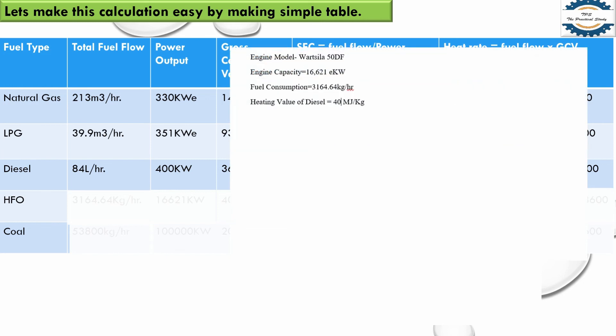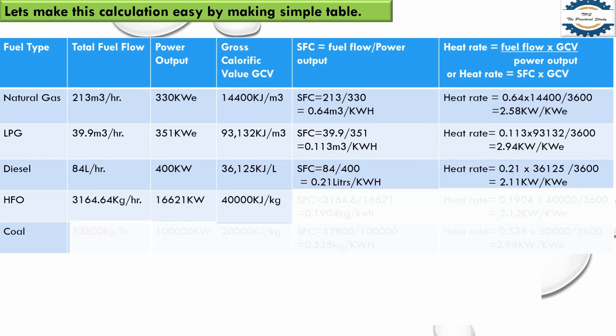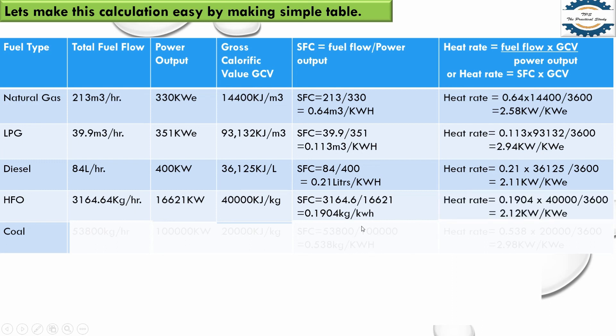For HFO, I selected a Wärtsilä engine 50DF. Its fuel consumption is 3,164.64 kilograms per hour and its engine capacity is 16,621 kilowatt — quite a large engine. The heating value of HFO is 40 megajoule per kg, which equals 40,000 kilojoule per kg. Dividing fuel flow by power output gives specific fuel consumption, and applying the heat rate formula, we get 2.12 kilowatt per kilowatt electric.